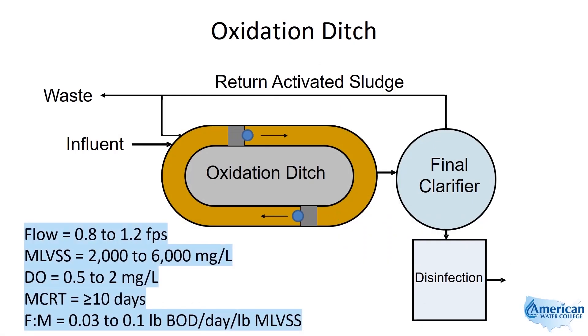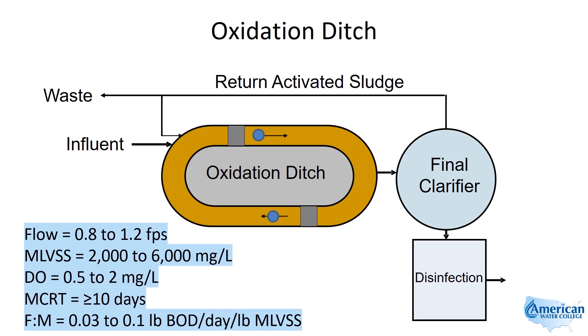The oxidation ditch is an extended aeration process, meaning it is a low-rate process with a relatively high hydraulic retention time in the range of 24 hours. The activated sludge is moved around the oval basin by rotors and brushes, which are mechanical aerators represented here in the picture by the gray rectangles on each side of the ditch. This type of system is used in small to medium-sized applications.